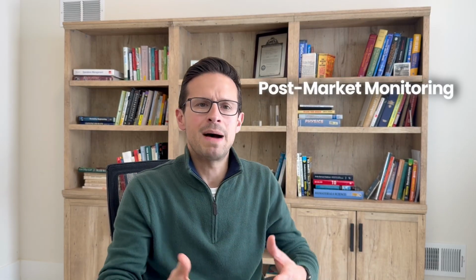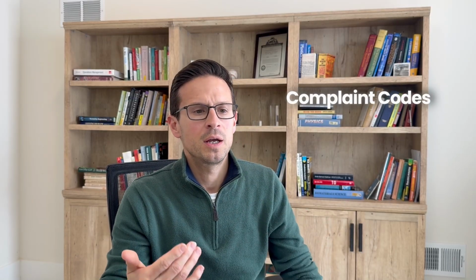Another requirement in design transfer that you can actually start earlier in the process that I don't think I touched on is setting up your post-market monitoring, your complaint management process. All that has to be in place before you launch the product: surveillance plan to define all your complaint codes. Ideally, you want to map those to your risk management process. That can be done early, even in your design output and V&V stages, but that's another element that's required for commercial launch.